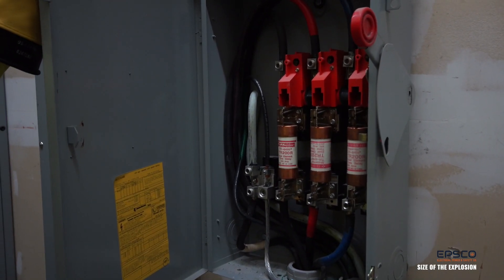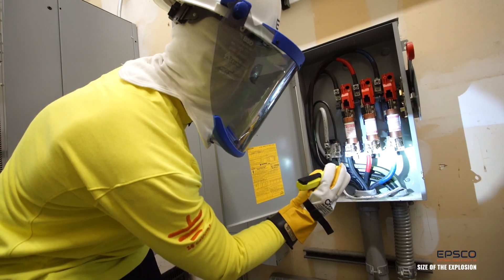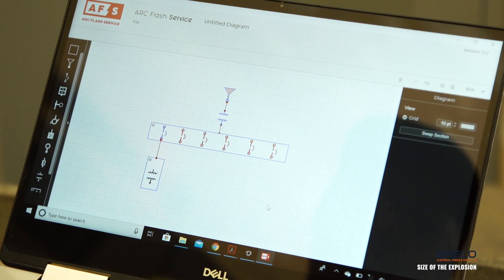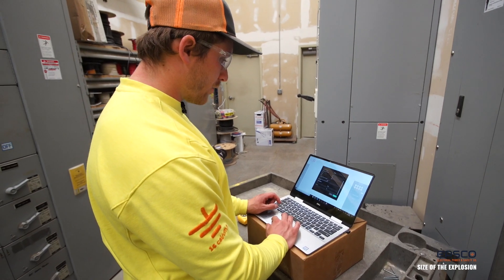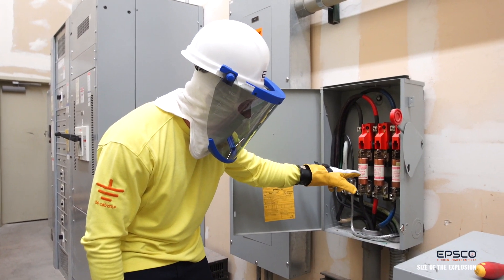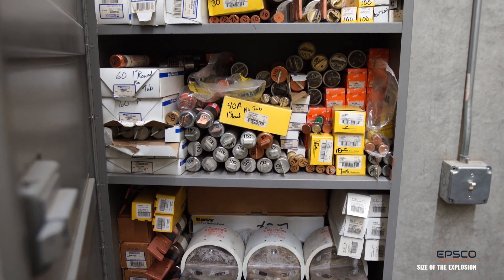There are some ways we can control arc flash explosions with engineering and design. Arc flash mitigation reduces hazards and risks by modifying protective devices and electrical infrastructure. You can find out more in the Inherent Controls section of the hierarchy of risk controls. Before you attempt any modifications to upstream protective devices, make sure to get engineering approval, because it all plays a role in arc flash calculations. If you turn up breaker settings to troubleshoot, or replace a fuse with a larger or different type of fuse, you can cause unexpected downstream hazards.